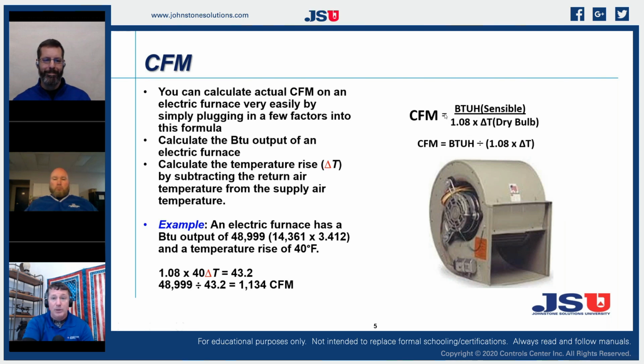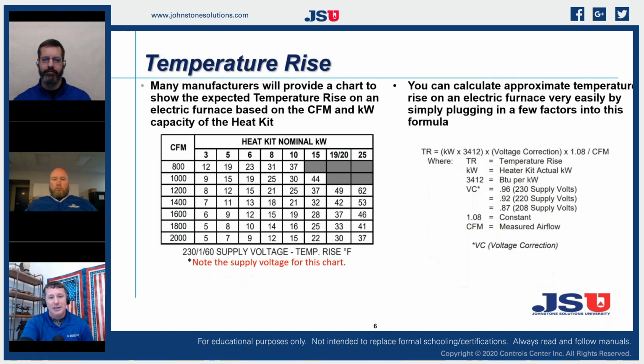But yeah, it's a good point. Make sure that thing is in emergency heat when we're doing this and the compressor's not running. Because remember, the compressor is also moving BTUs, right? So we're just going to be looking at the efficiency of our electric heat strips right now. And we're doing this to make sure that we have a proper temperature rise on our electric furnace, because electric furnaces do rely on a temperature rise. It's not on the nameplate like it is on a gas furnace, but we do rely on a temperature rise on that.